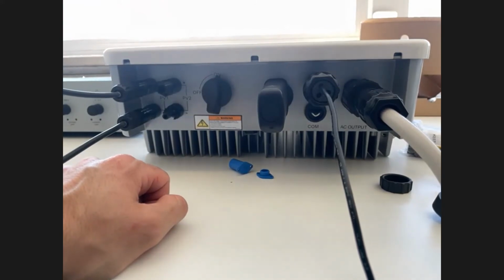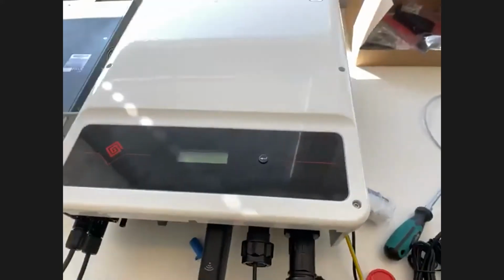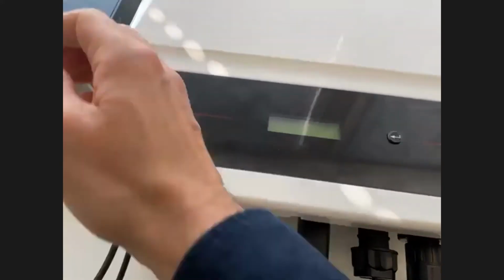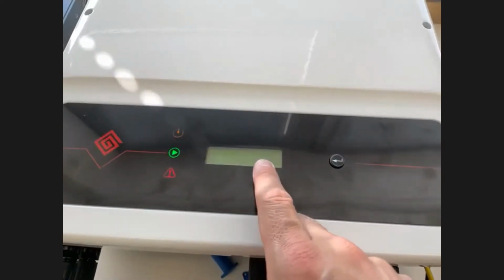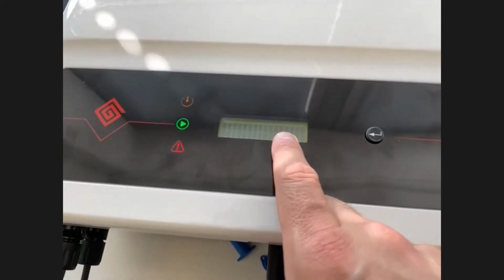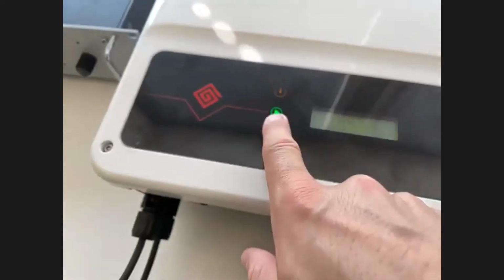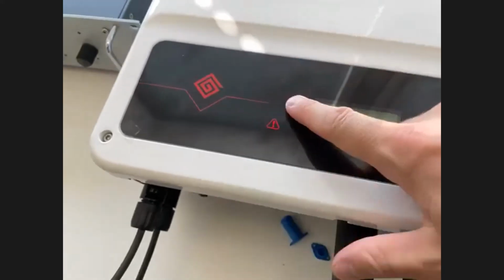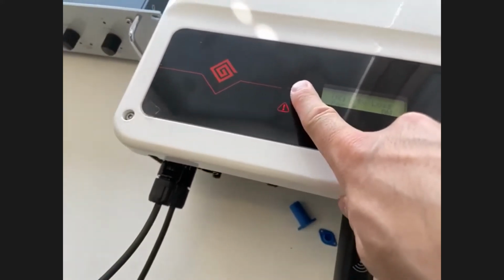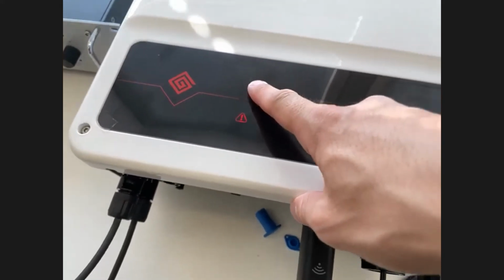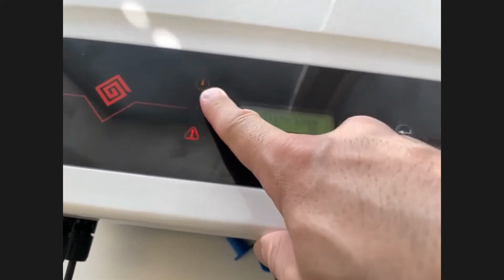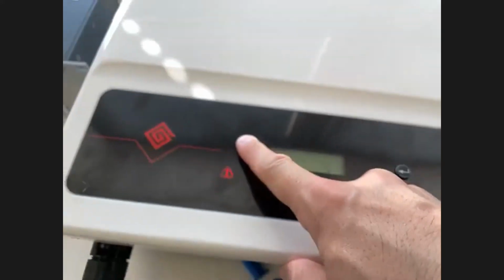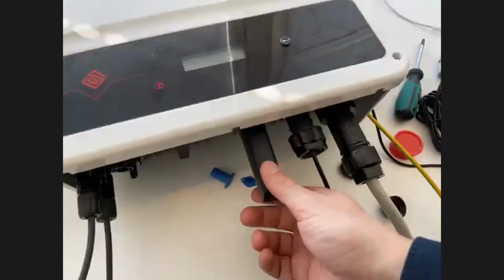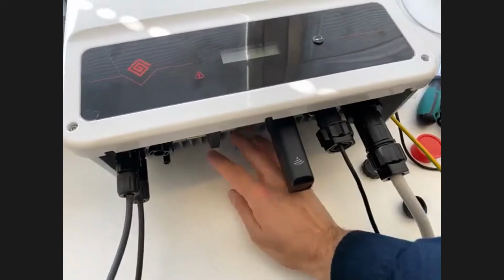And then when you turn the DC switch on, it takes a while, but then you will see here on this one, it actually has a display, so you could commission it directly on the inverter. We will, however, use the app. And now you see that it will turn on. So this one starts shining, but then it's off because it's not feeding any power right now. This one is blinking 2 times and then off. And that means that there's no connection to the internet.